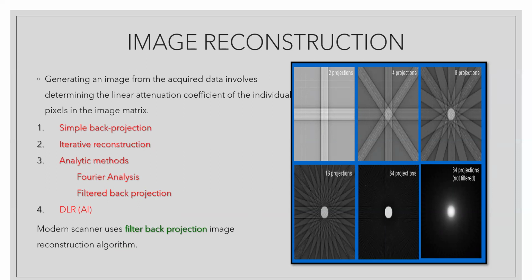And coming to the last one, DLR. What is a DLR? It's deep learning reconstruction. It is a newly upcoming thing, which is artificial intelligence. Why do we need artificial intelligence in the algorithm of a CT? Because of high image quality, low radiation dose and fast reconstruction. Here, the DLR algorithms are currently trained prior to installation, making their intelligence static rather than a dynamically learning system. Canon and GE have recently launched their versions of DLR.